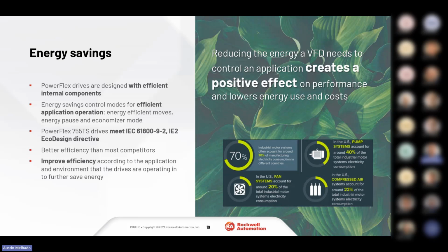So a conveyor might be one example. As a conveyor is running and there are different loads, or there's no load, the VFD will reduce its command for motor flux current. So it's just saving that extra energy that might not be needed. From an hour to hour or day-to-day perspective, it might be minute, but if you look at it from a yearly, long-term perspective of having these modes applied, we could really see some energy savings for the end users.